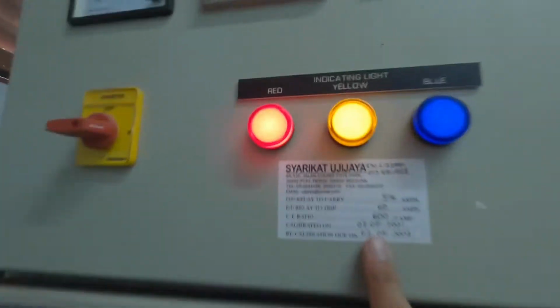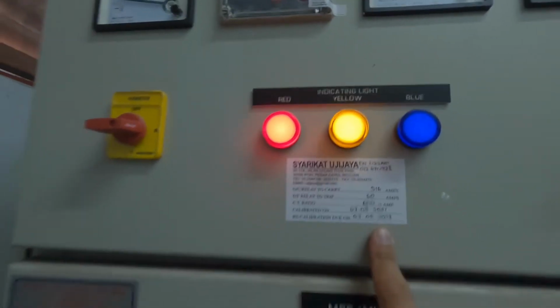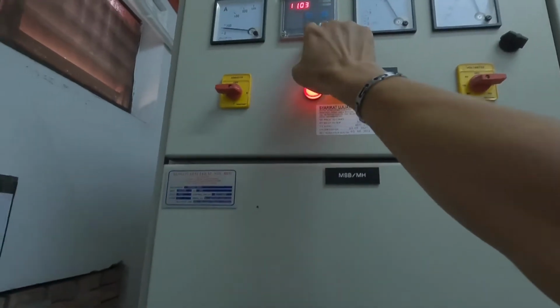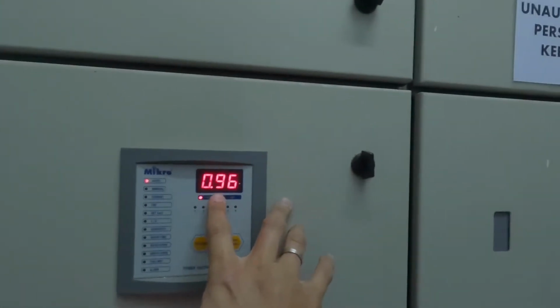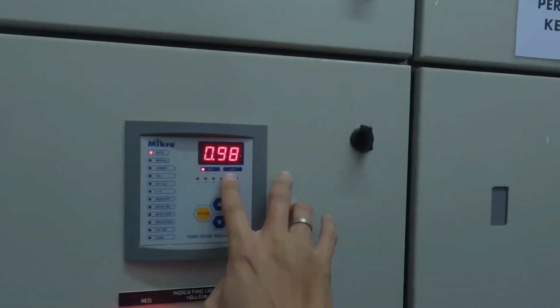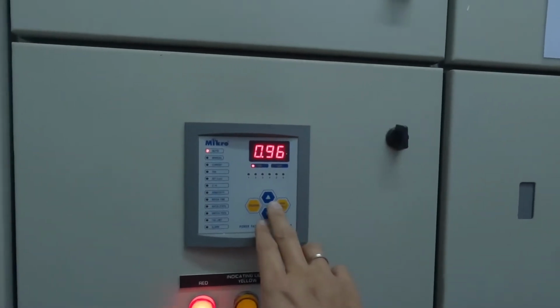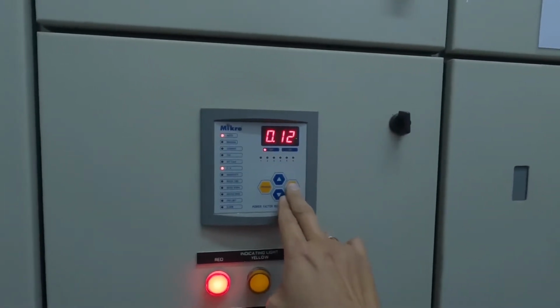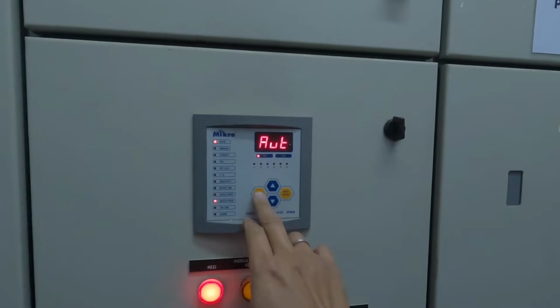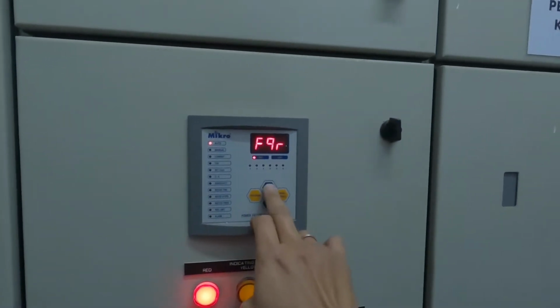Alright, so calibration is up to date, expiry on 2023. Okay, relay is in function, no problem. Power factor, okay, 0.96 above 0.85. Okay, let us test all the capacitor bank to make sure capacitor bank is in good condition.